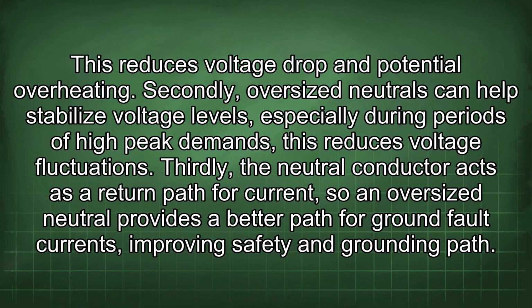Secondly, oversized neutrals can help stabilize voltage levels, especially during periods of high peak demands. This reduces voltage fluctuations. Thirdly, the neutral conductor acts as a return path for current, so an oversized neutral provides a better path for ground fault currents, improving safety in the grounding path.